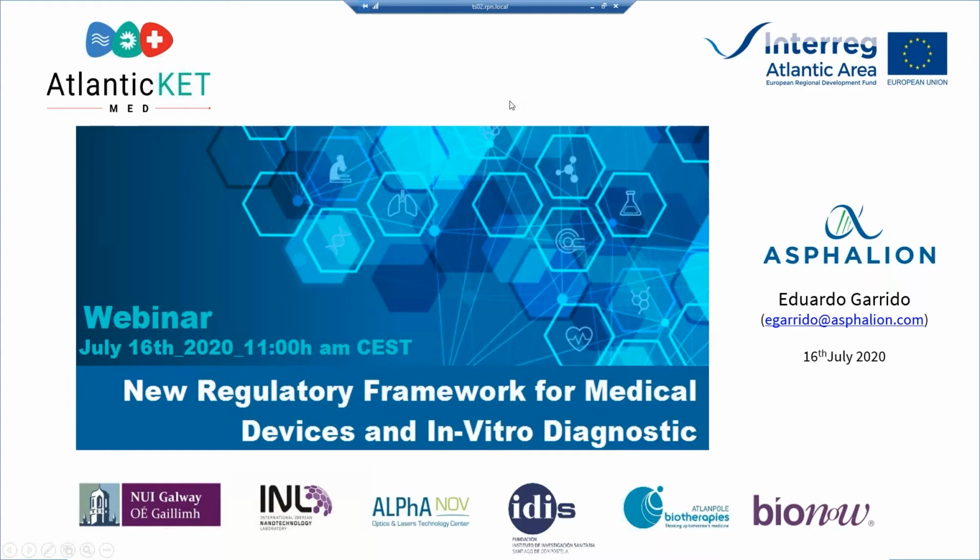So I see another question here: for medical devices composed of different modules or components, should they be tested and certified as integrated systems, or can the individual module components be tested and certified separately? Certified separately, yes, you can, depending on your approach. You can either test together or separately. But as I was saying in the question before, you have to demonstrate compatibility within the system.